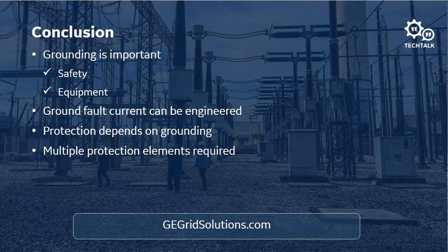When we engineer our grounding transformers, what resistance do we want to use? So the neutral resistor is typically chosen such that the power dissipated in the resistor during a single line to ground fault is approximately equal to the reactive power produced by the zero sequence capacitance of the stator winding and the generator's step-up transformer low voltage winding. So you need a couple of pieces of information, specifically the zero sequence capacitance of the stator winding. You might or might not have that information. That might need to come from the manufacturer, when they're designing the generator. It could be empirically calculated. I'm not sure if there's a method to actually measure it, but that's one of the components you'll need to determine that neutral resistor.